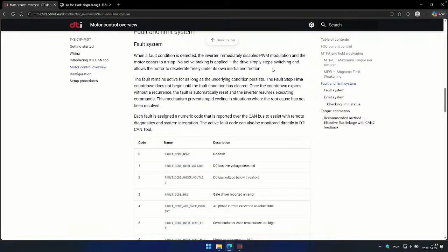This is restored automatically by the fault stop time parameter, which can be set and determined by you. You can set it to 100 milliseconds if it suits you, or you can set it to 5 seconds also. This fault stop timer starts to count down when the condition is cleared. So, for example, if the overvoltage condition is not active anymore, it starts to count down and recovers into a no fault condition, and you can continue the operation. So a fault stops the modulation immediately because it assumes some critical issue.